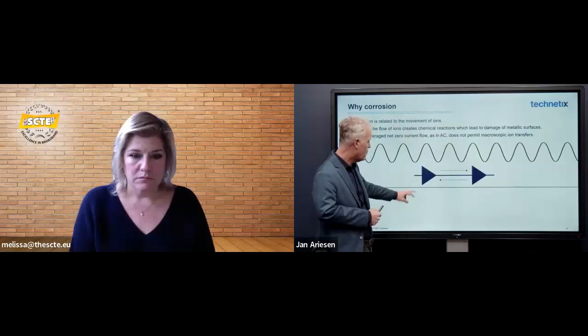We go to a switched DC network, or a low frequency AC signal. So for instance, 89 volts positive, then we go to 89 volts negative, and at a certain time back to 89 volts positive. We constantly switch the voltage to avoid corrosion - still a DC signal at each point, but we swap it to create a positive and a negative current, giving us that 0 current flow, and therefore we don't get the corrosion.